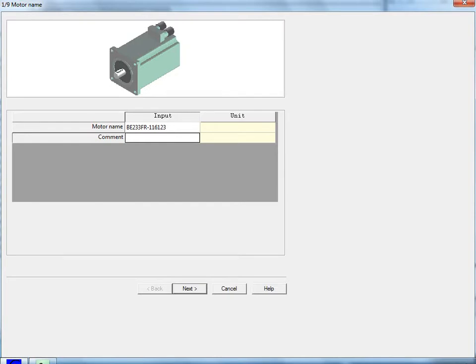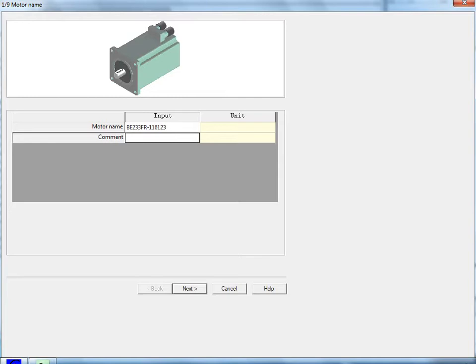Each time you use 'use as template,' it will always set the name as 'copy of' and then the standard motor part number. So if you do multiple motor files, it will always have the same name. The last one created is on top of the list. If you ever connect to another drive and do an upload, if it's a custom motor, it will also import that motor file. You can look at the summary screen to see the differences, but in the drive configuration, it would be difficult to determine which is correct. So it's good practice, go ahead and rename it.